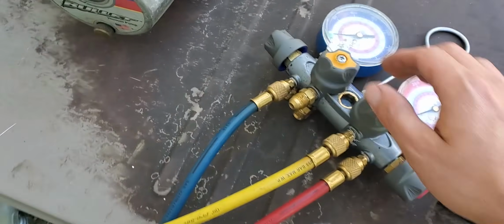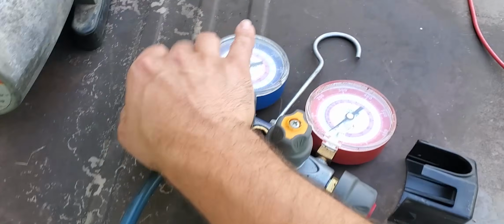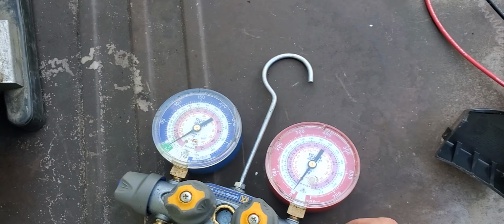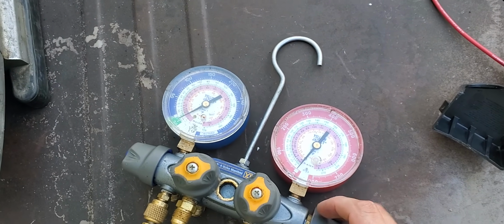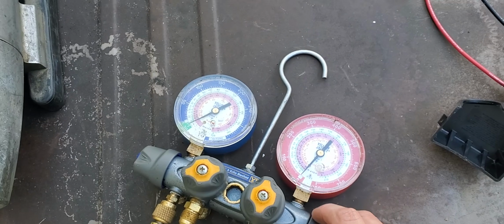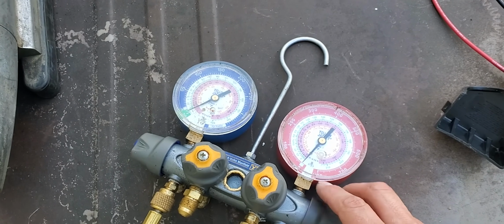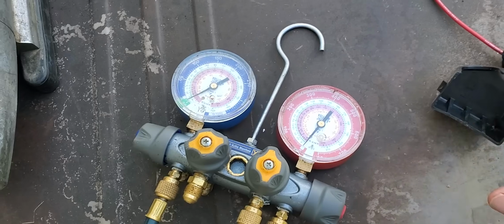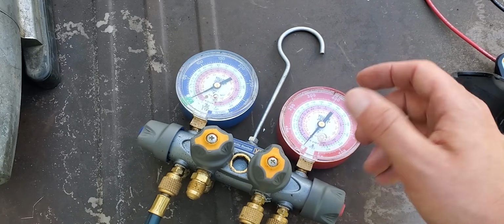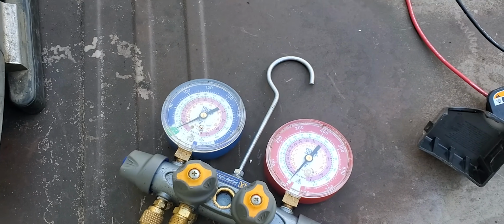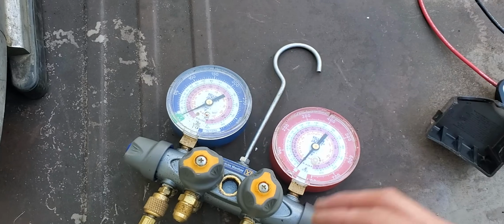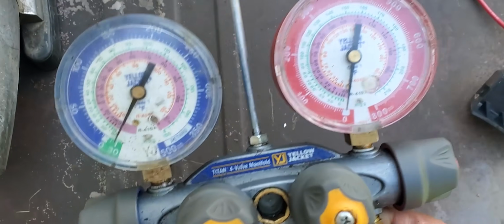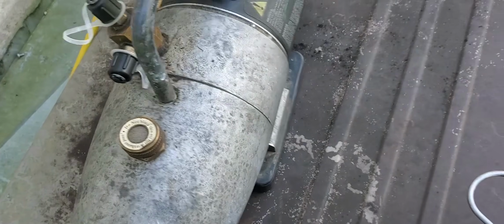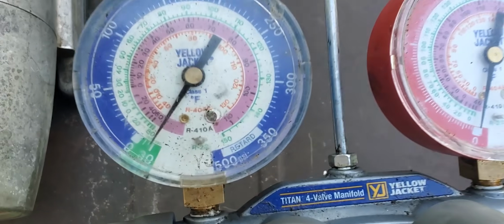All right, so after you vacuum, you shut your gauges off. And if you have a micron gauge on, the micron gauge will begin to rise if it's leaking. So if it's at 250 after you stop, then you shut your gauges off, turn the pump off, and it goes up to 500, 1,000. You know it's leaking still. If the pump changes sound when you turn the pump off, then it still needs to be vacuumed.